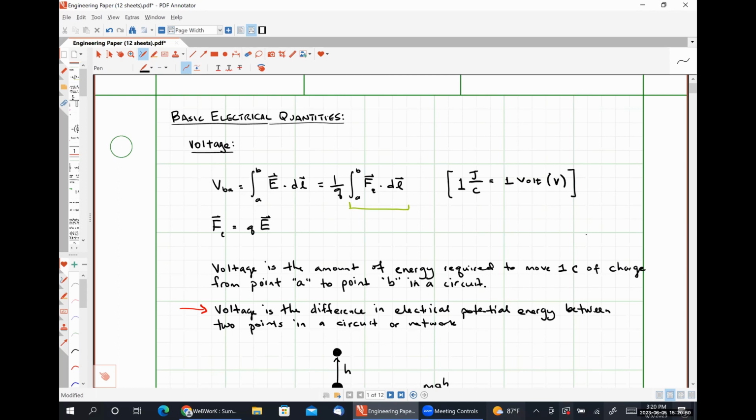The length of your conductors can play a large role, especially in larger systems, right? If you're going to go out into industry where you might be running cable runs over several hundred yards through conduit and all this kind of stuff, you need to really pay attention to the size of the conductors that you use, because if they have a larger cross-sectional area, they tend to have a smaller resistance, which means you can get away with using longer runs without seeing appreciable voltage drops. And we'll talk about that a little bit in tomorrow's class.